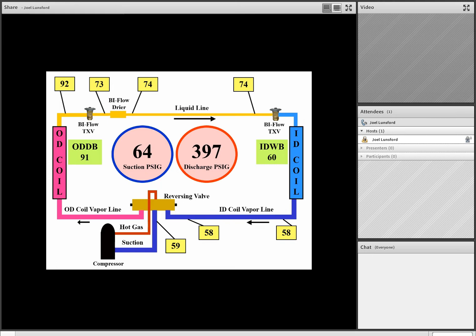And in this example, we see that we've got a restricted outdoor check valve again on our outdoor TXV. We're in the cooling mode of operation, and we have a large temperature difference, a 19-degree temperature difference across our BiFlow TXV outside. But we also notice our suction pressure is low, our superheat's high, our subcooling is elevated, and our discharge pressure is high. Liquid circuit restriction, and we find that by taking accurate temperatures across the liquid line components.